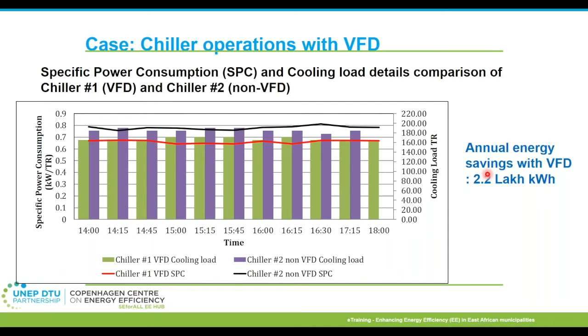So it gives you a picture that on having a variable frequency drive for variable loads, the system with the VFD is dynamic enough to respond to the loads being demanded, and it can optimize its energy consumption accordingly. On an annual basis, the difference is about 2.2 lakh kWh: the one with VFD was consuming almost 2.2 lakh kWh less compared to the one without VFD.